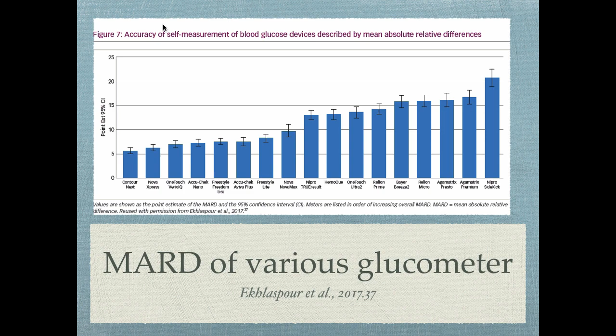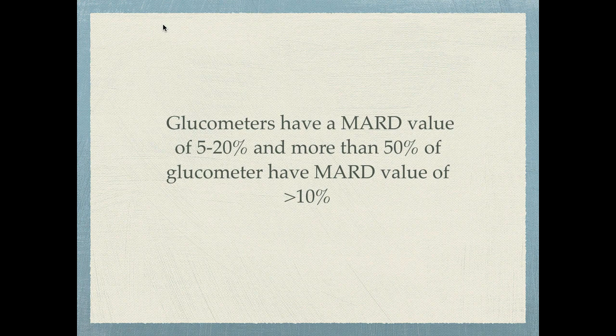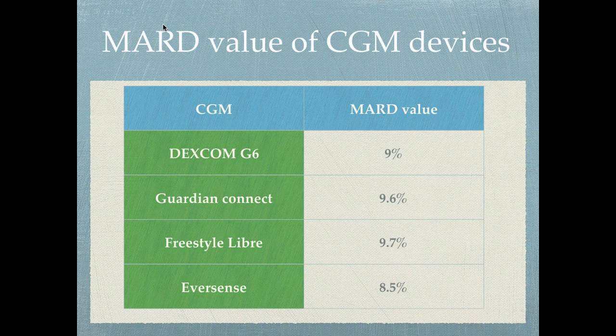You can see this chart over here. Most glucometers had MARD values of between 5 to 20%, but more than 50% of them had a MARD value of greater than 10%, right? So basically what I'm going to tell you is that glucometers also are not very accurate per se, right? And this difference remains. And look at this MARD value of CGM devices: Dexcom has 9%, Guardian has 9.6%, Libre has 9.7%, and Eversense has 8.5%. So most of them play around the range of 8 to 10%. So what you see is that the CGM devices have a MARD value which is less than 50% of the glucometers. So what I'm trying to point out is that actually CGM devices are probably as accurate or more accurate than your blood glucose monitors. So most current CGMs are as accurate, or you could say as inaccurate, as the BGM devices. And remember, this new movie, it's a great movie, go watch it. It's called Mard Ko Dard Nahi Hota, right? So there you go.